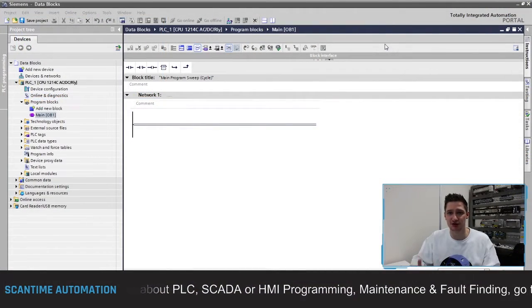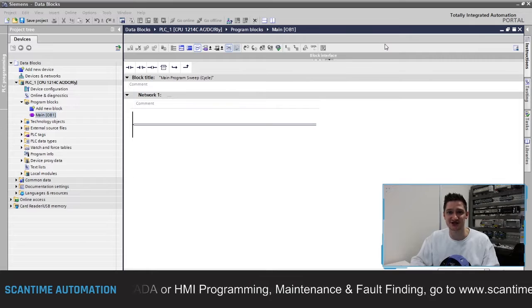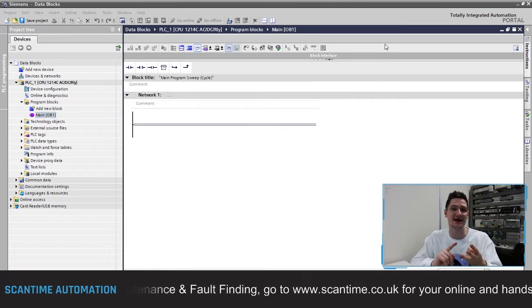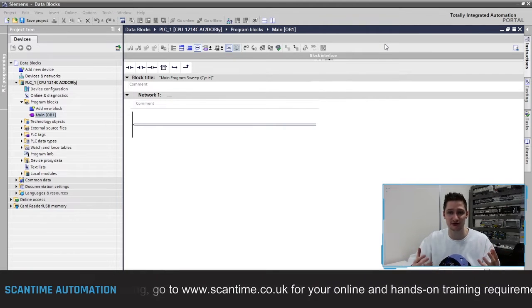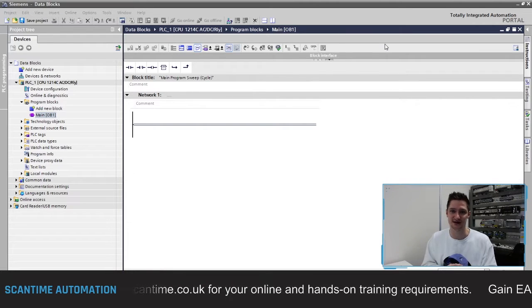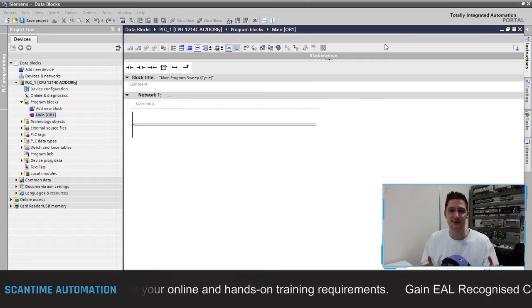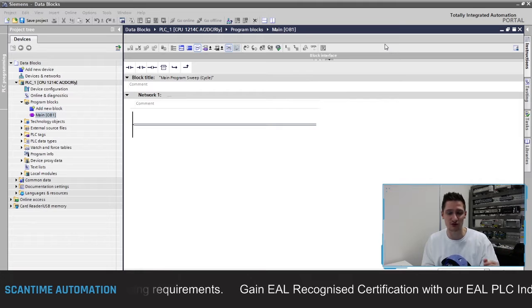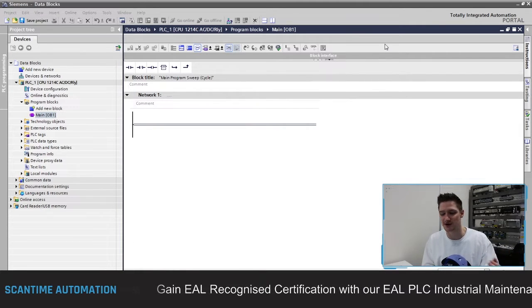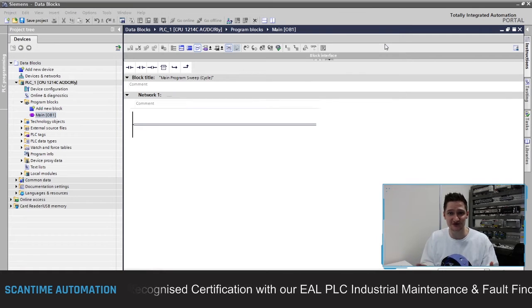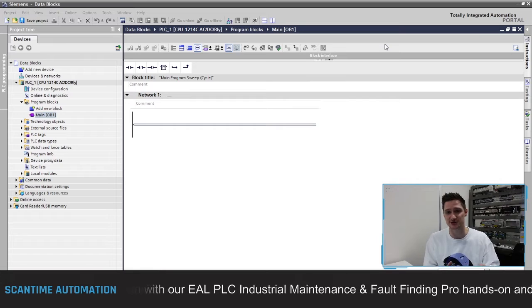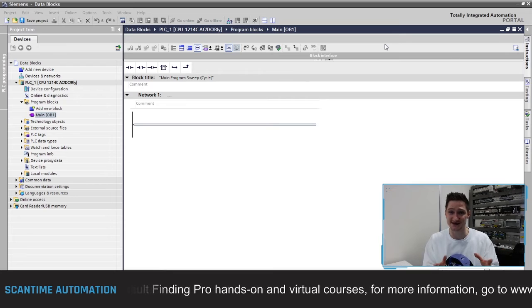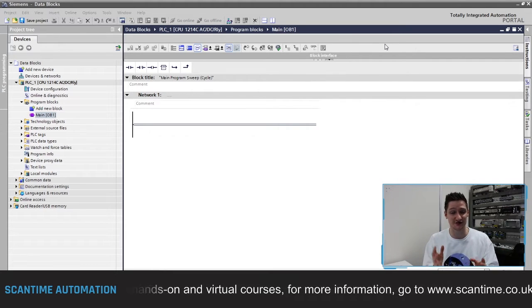We recently worked on a pressure testing system for a client where you can undertake three types of tests: a low pressure test, a medium pressure test, and a high pressure test. Each pressure test collects information from the real world and we store that inside of the PLC. In other PLCs you would usually store that inside of data memory areas — Omron uses DM registers or D registers, Mitsubishi uses D registers. Siemens also has memory bytes, memory words, and memory double words, but we saw problems with overlapping data memory areas fairly easily and corrupting data.